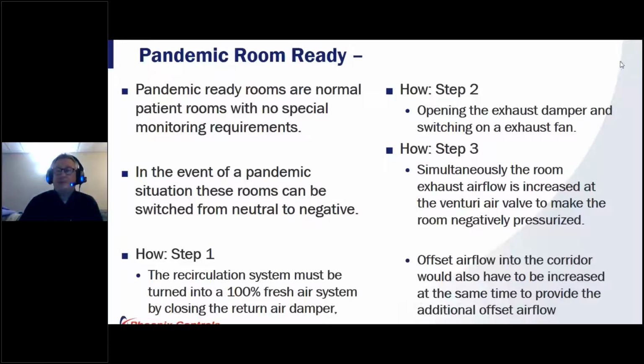Now, the most important thing here is to make sure that we compensate, right, for that offset air. Once you increase your exhaust air to those spaces, we don't want to have to steal any air from any of those surrounding or adjacent spaces. So in order to accommodate that additional exhaust air, we want to bring in more supply air in the corridor, right? That's feeding those spaces. That way we don't starve the other spaces within that zone.